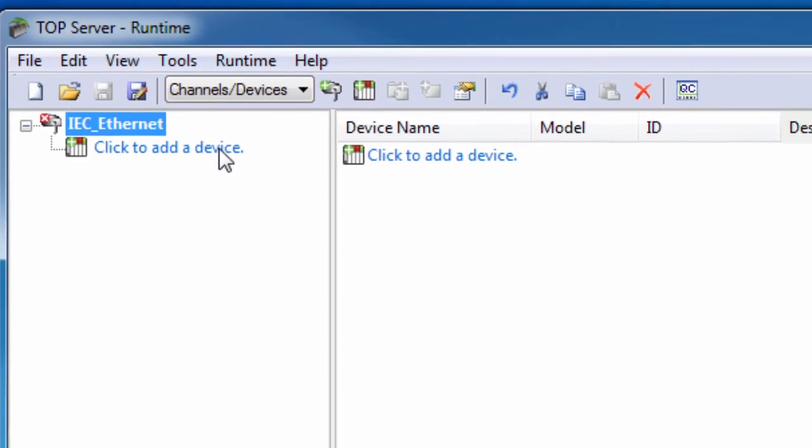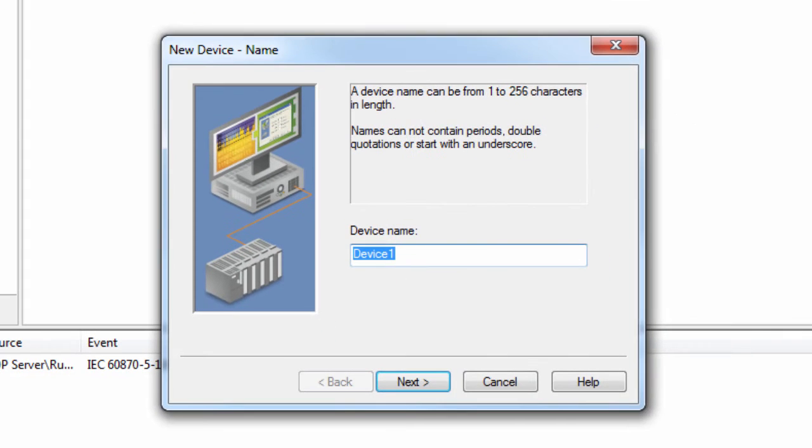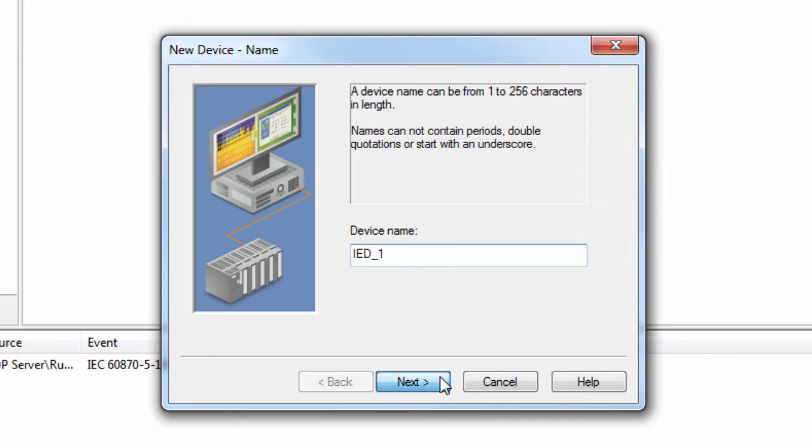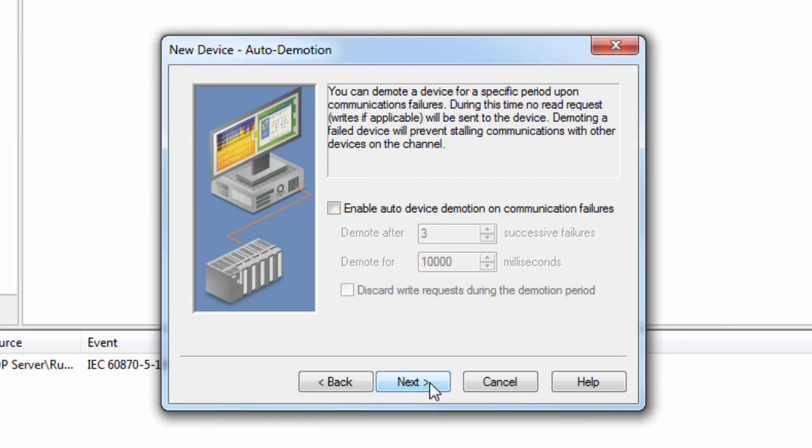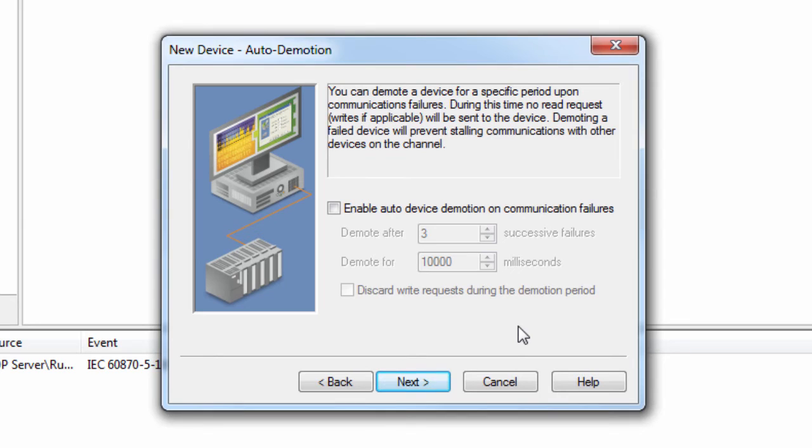Next, click to add a device. Give the device a friendly meaningful name. I will call the example device IED1. Click Next to review the scan mode. We recommend leaving this setting at default. Click Next to define whether or not to use auto demotion to take unresponsive devices out of the polling cycle for a specified period. We recommend leaving the setting unchecked during the initial configuration. You can always go back and change this if you find you need it.